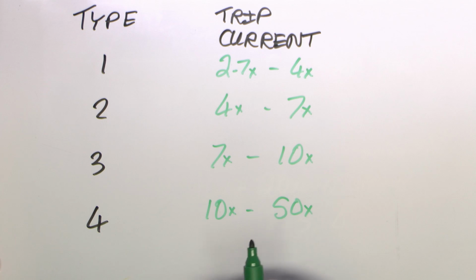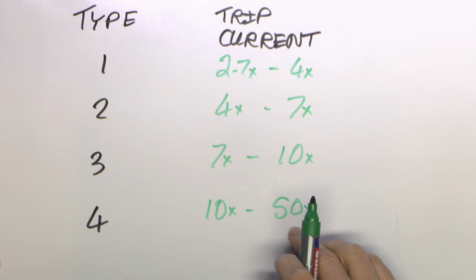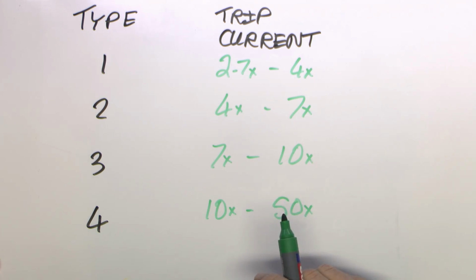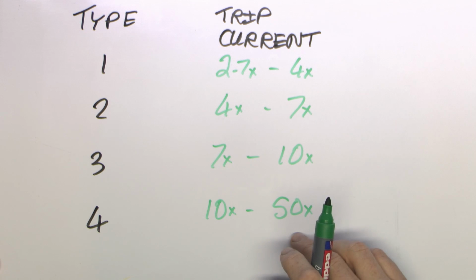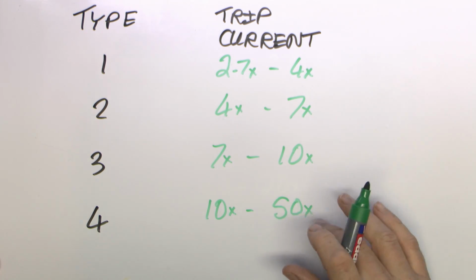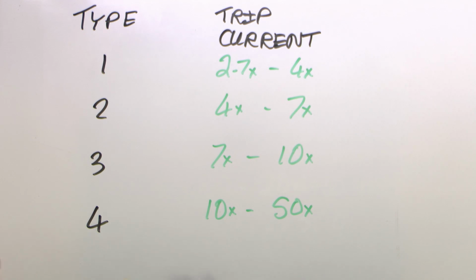And again, some of these other ratings here may be slightly different for different manufacturers. The problem with the type 4, if it does go up to 50 times, and you had, say, a moderately rated item, then the current to trip it could actually be so massive that you would never be able to get that from the supply, in which case if a fault occurred it wouldn't actually disconnect. So in theory they're up to 50 times, but in reality well worth getting the specifications for that particular one, because the manufacturer may have made it to a slightly different range, so well worth getting that to check. Type 4s are fairly uncommon, not likely to be seeing many of those around, but type 1 and 2 is fairly common, and even type 3s do still show up.